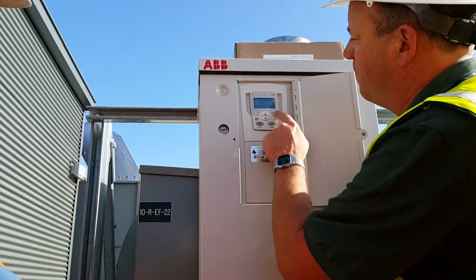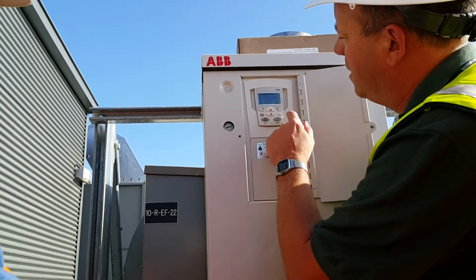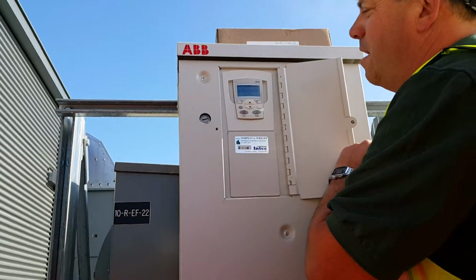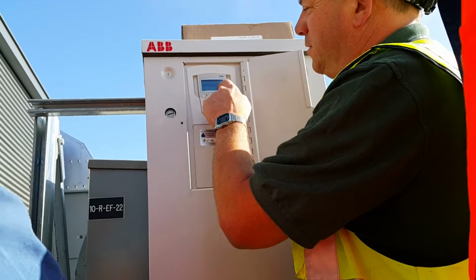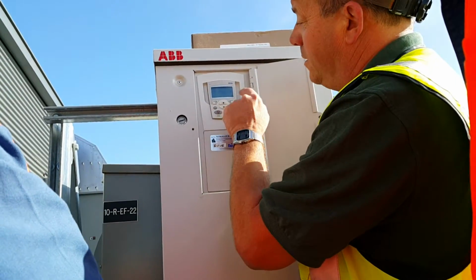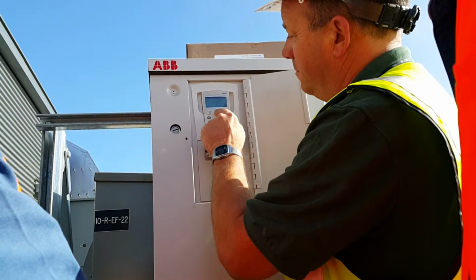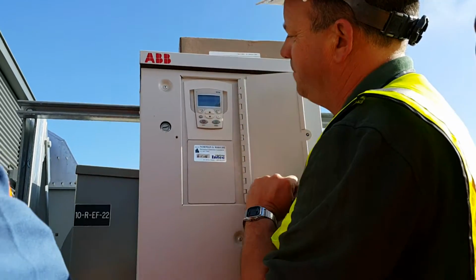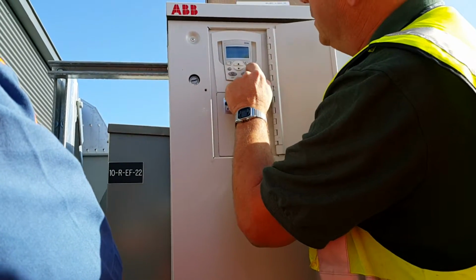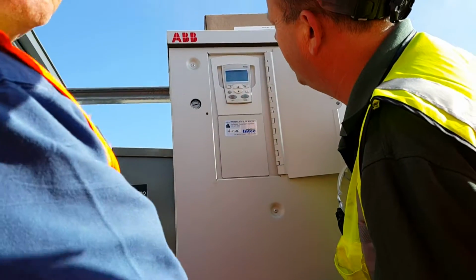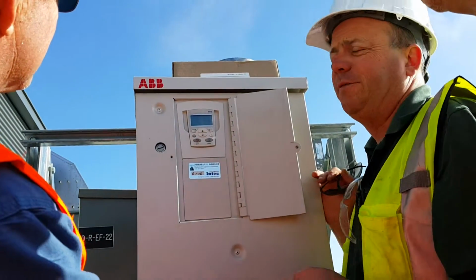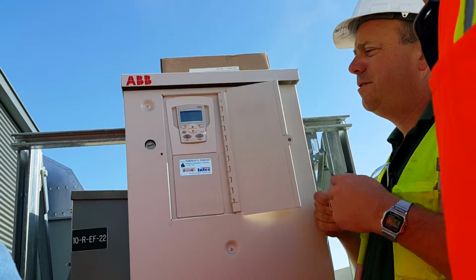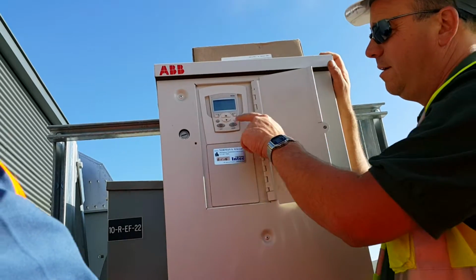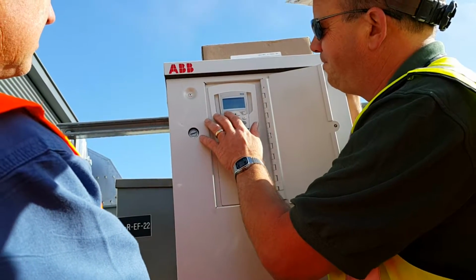Now we go into that group further to where we actually go to the parameters, and let's say we go to acceleration time number 1. What does that mean? Right now it says 30 seconds. We can edit it if we wanted to, up or down, save. But what does that mean? It says sets the acceleration time from 0 to maximum frequency for ramp pair 1. So lots of information right here with the help key.